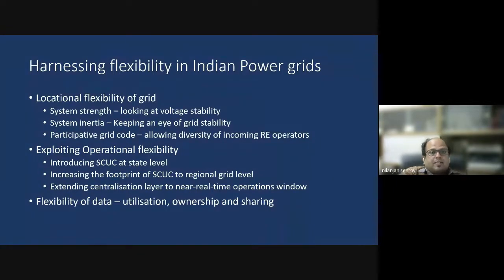System inertia is the second aspect of locational flexibility that we talk about. In system inertia, I hope you know that inertia is used in the context of system frequency and its reluctance to change due to unexpected load generation unbalance. And this is also related to the mechanical moment of inertia of the rotating shafts of all the synchronous machines connected in the system.